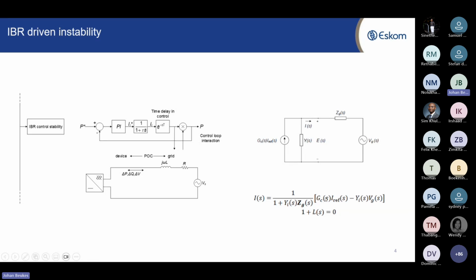What is important to note here is that two things influence the current that you inject into a grid. The grid following inverter can be modeled as a current source, and the two things at play here are, first, the reference that is created from a power reference, for example, or a voltage reference. You get a current reference. And then the transfer function, the second one is that the grid is also changing the current shape.